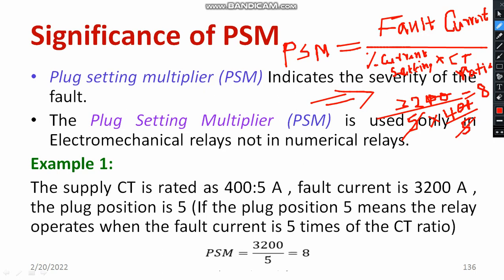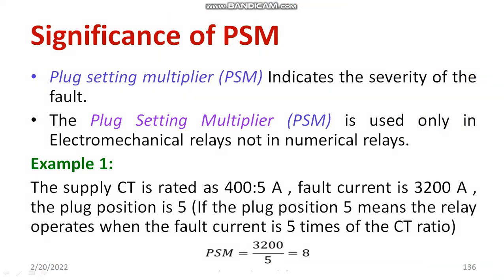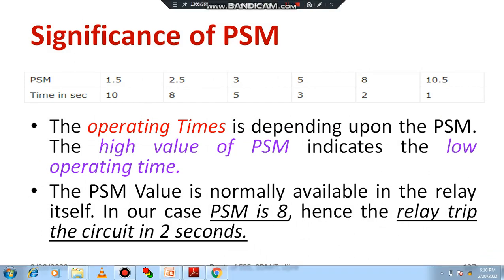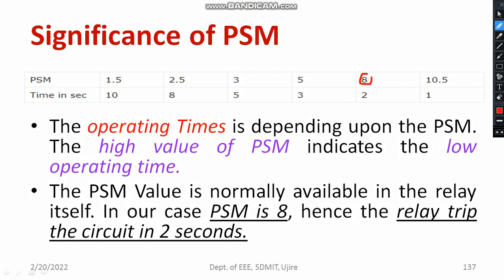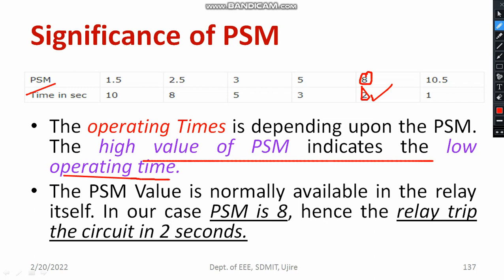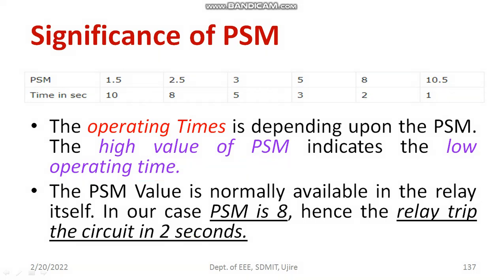Here you are supposed to multiply 5 into the CT ratio, which is 400 by 5. That gives the answer — PSM is 8. Now, corresponding to PSM equal to 8 from the table, the operating time is 2 seconds. The operating time depends on the value of PSM. A high value of PSM indicates low operating time, meaning if the severity is high, the relay has to operate quickly. The PSM value is normally available in the relay itself. In case PSM is equal to 8, the relay trip time is 2 seconds, as is clear from the table.